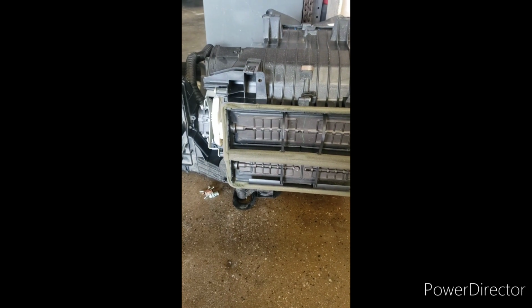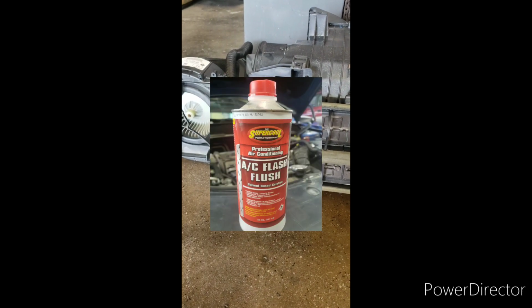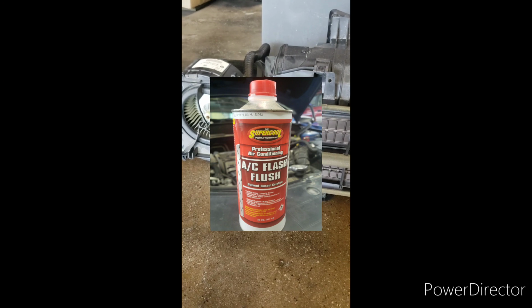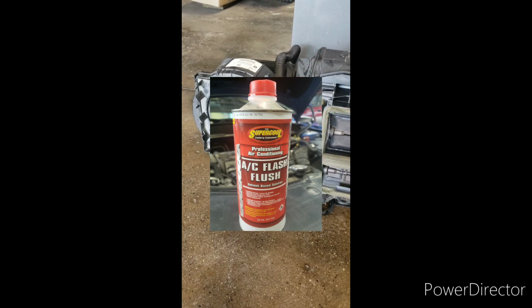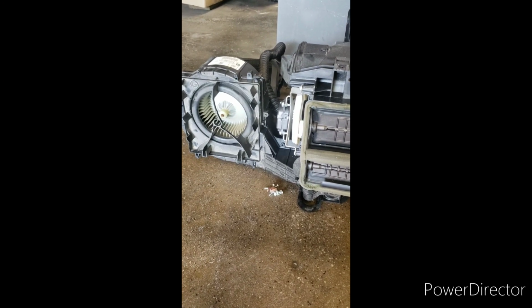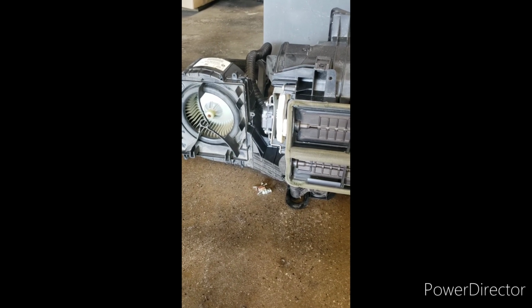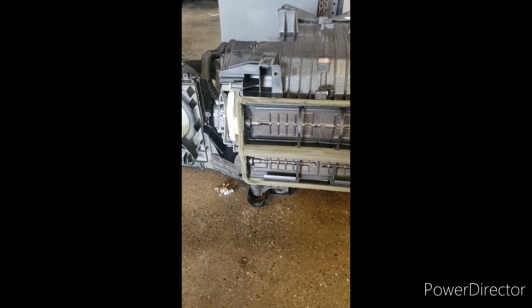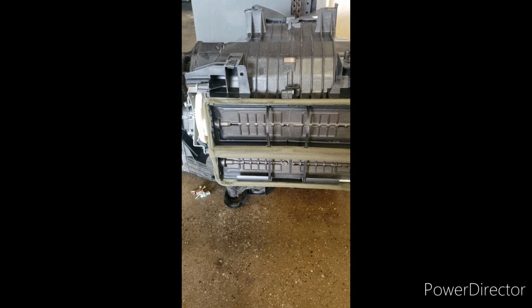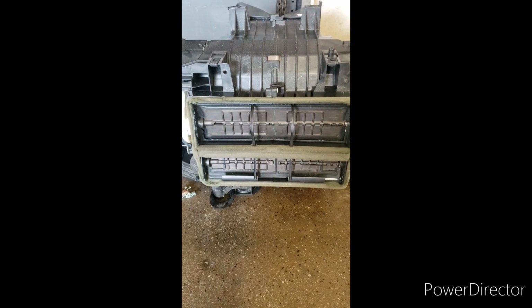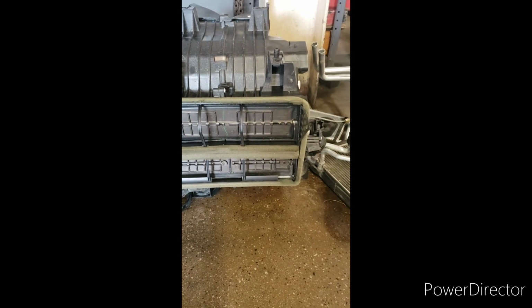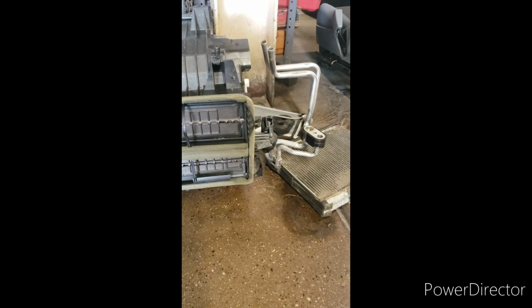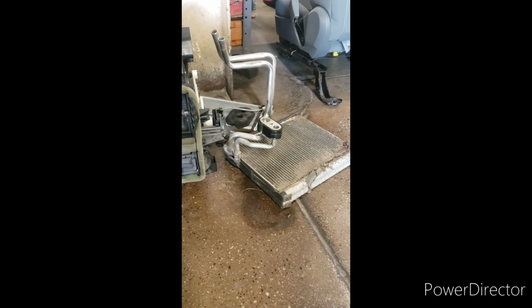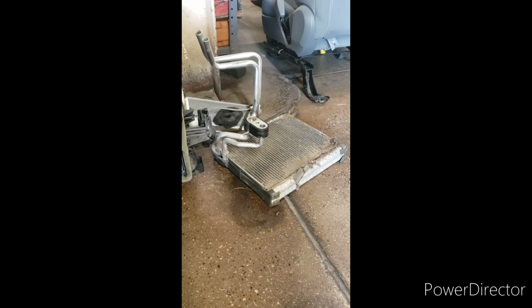In a perfect world, I would flush the whole AC system out and start from scratch, and you know exactly how much oil to put in if you don't have a machine that tells you what you just pulled out. So most of the time when I do compressors and condensers and a whole compressor kit - actually, all the time - I do flush it out and make sure the oil is properly balanced.